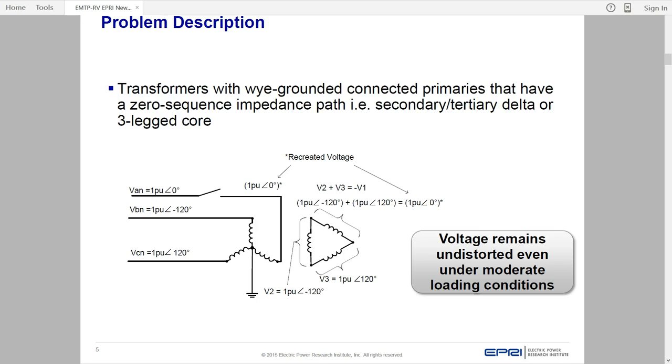Well, what we came up with was a method to actually detect that zero sequence impedance. And when you get an open phase here, and you're sitting there at no load, you get a substantial change in that zero sequence impedance because of, it's a little bit hard to draw, but you can kind of think of it as a three-legged core.